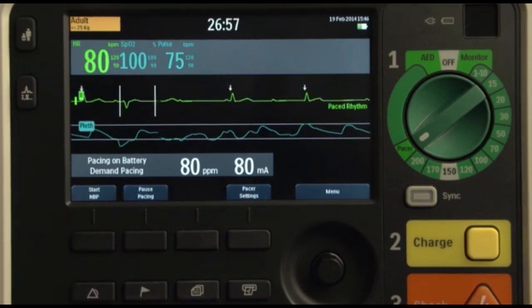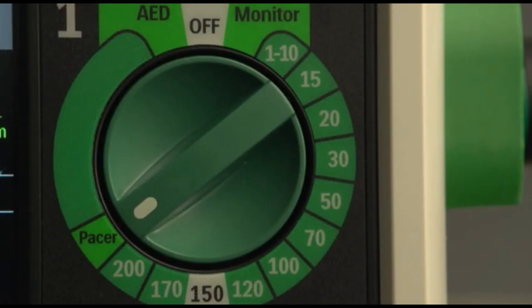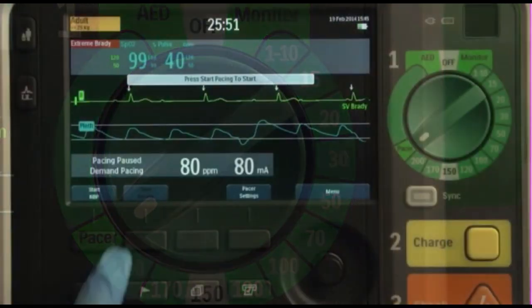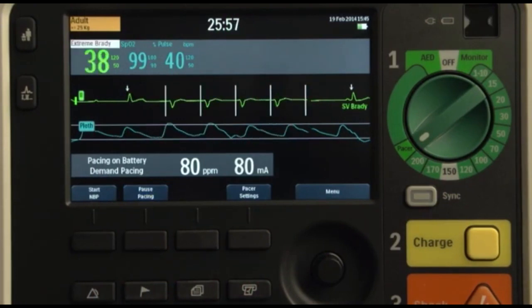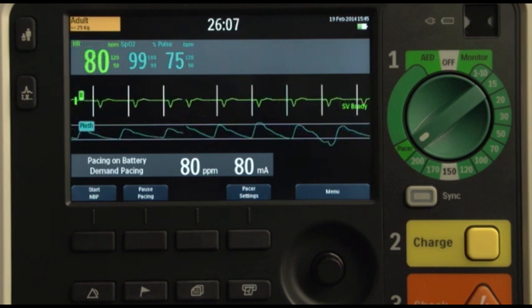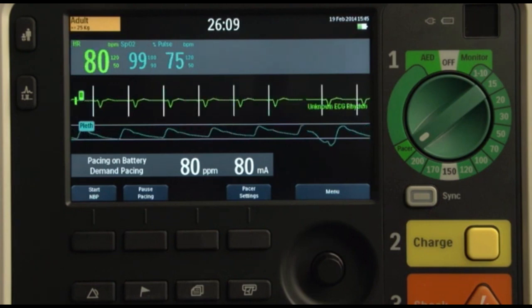During demand mode pacing, defibrillators detect R waves or beats. Intrinsic beats are defined as those that are generated naturally by the patient. Paced beats are defined as those that are a result of delivered pacing energy. Philips ALS defibrillators also define the paced refractory period, which is simply a period of time after the delivery of a pace pulse.